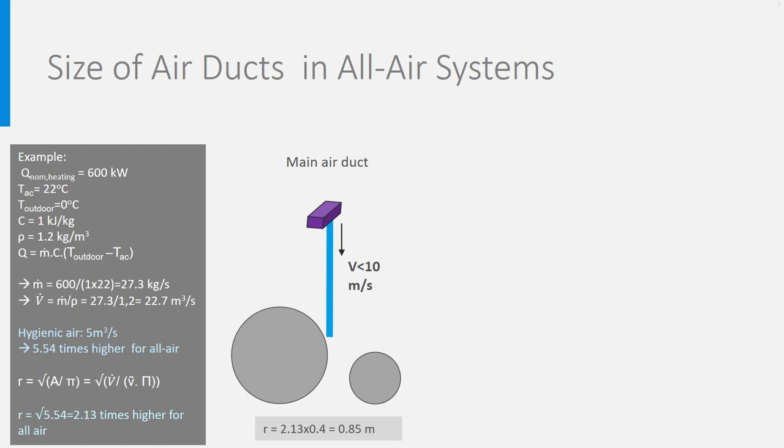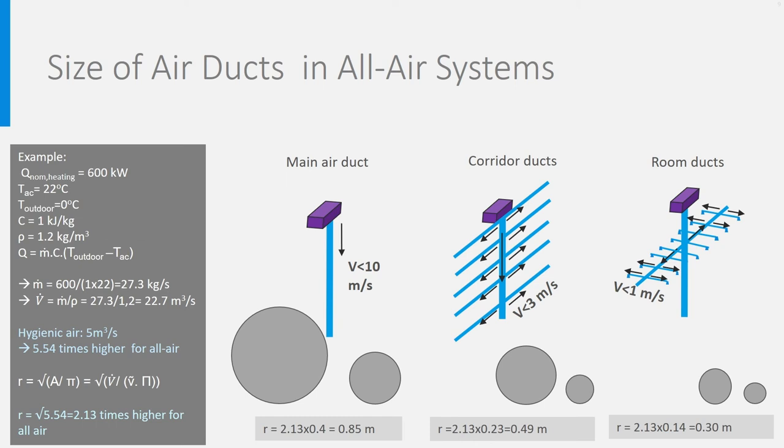In our case, this leads to a main air duct of 1.70 meter diameter, corridor ducts of 98 cm, and room ducts of 60 cm diameter. This means something for the spatial design and the space the architect should reserve. If the pipes are also meant to transport cold air, you also need to check that the pipe sizing is large enough to transport the needed cold. You will then choose the highest diameter of both heating and cooling modes.